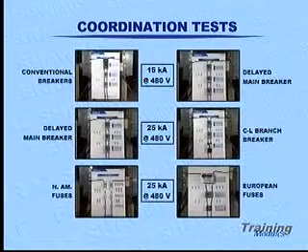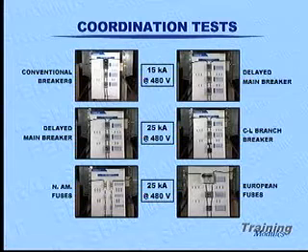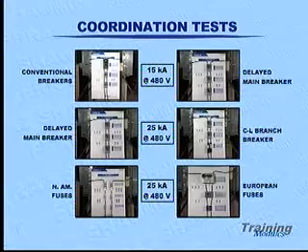6 tests will be run, with various protective types connected in series, respectively rated 200, 50, and 25 amperes. A downstream short circuit closing switch will initiate the fault.